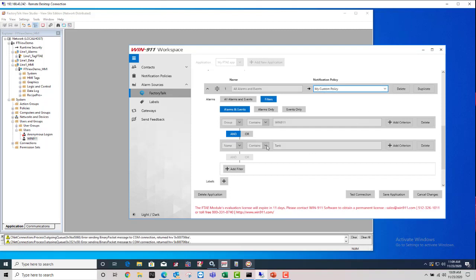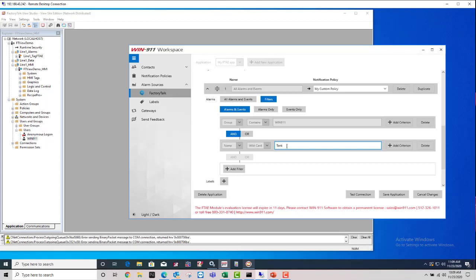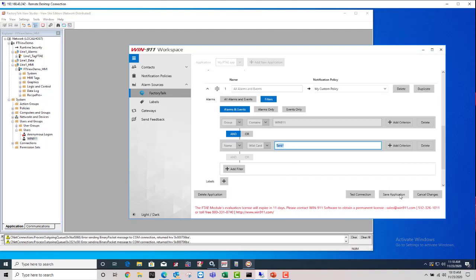Now, if you don't want to use the contains, the other option here for wildcard might be better if you have multiple tanks, for example. So if you had tank 1, 2, 3, 4, 5, however many you have, you can just do tank star, and that's what that wildcard field is for. It gives you the option to enter in that asterisk, that star, and it'll say it'll match anything with tank and anything after that. So this will grab tank 1 and tank 2 and et cetera all the way through anything that matches tank with something after it. And you can save that.